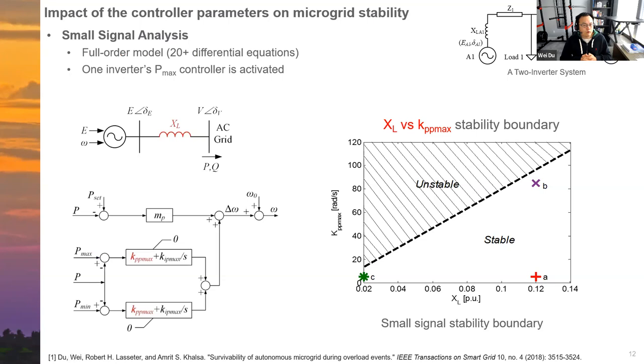Okay, so after talking about the overload events, another important finding from this CERTS microgrid is the small signal stability boundary. When we did this work, we wanted to understand how to design the parameters for this Pmax controller, and we found a small signal stability boundary. We found that the value of the coupling reactance is very important for the small signal stability boundary. You can see here we found this two-dimensional stability boundary. A larger coupling reactance allows a larger proportional gain of this Pmax controller to maintain the stability. And this stability boundary also applies to the droop control gain. So it's a very similar linear stability boundary that we found from this study.